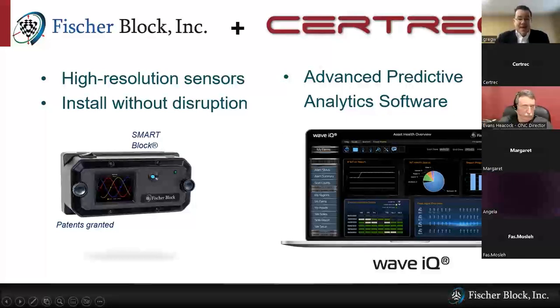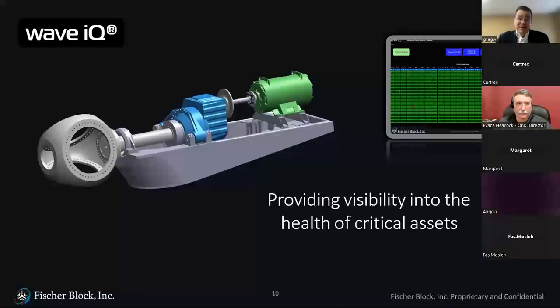Is there access to the back of the panel, or is it purely a front panel view of the equipment? And so over the years we have developed a number of different connection brackets so that we are able to install our sensors without an outage, without adding new wiring in most cases, and then stream the high resolution data to our software that is then analyzing the waveforms on a continuous basis and looking for slight distortions in those waveforms and associating them back to the inner workings of the assets involved.